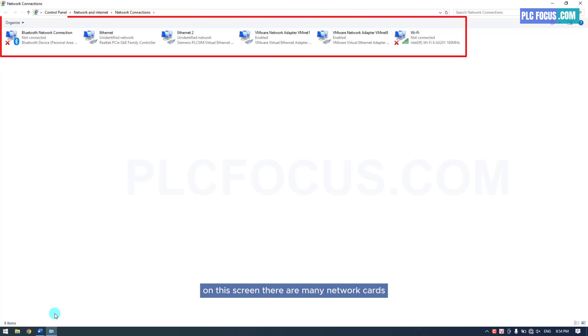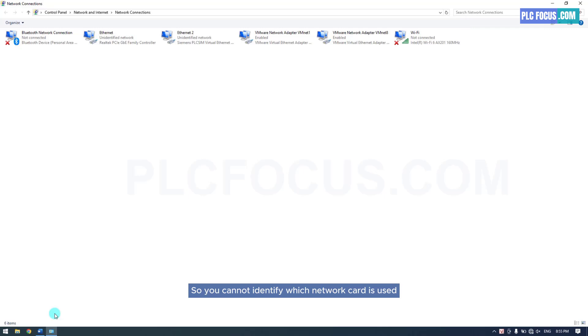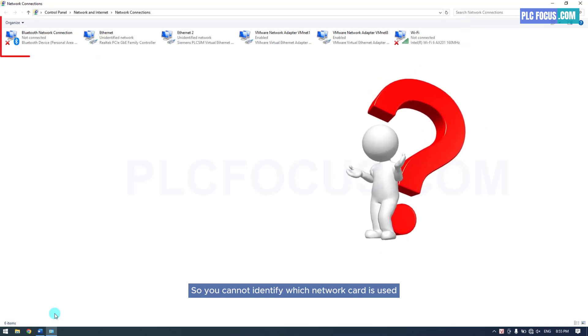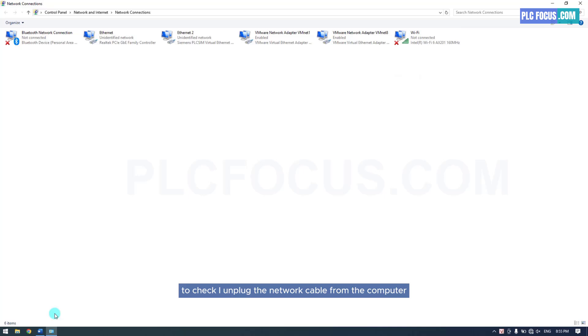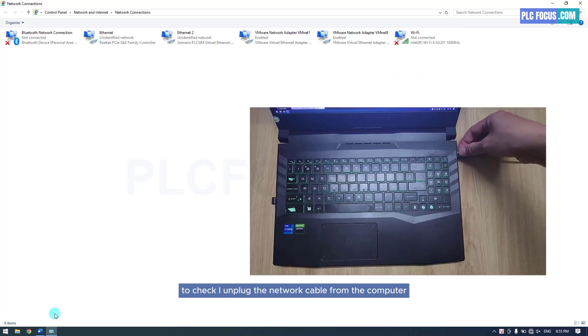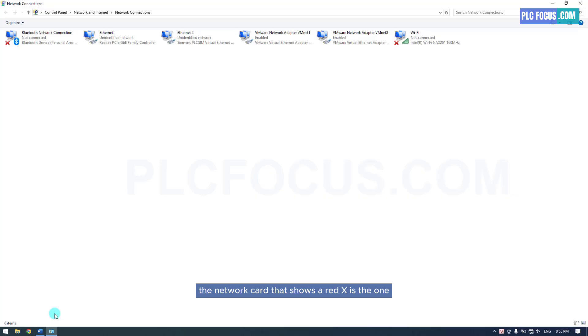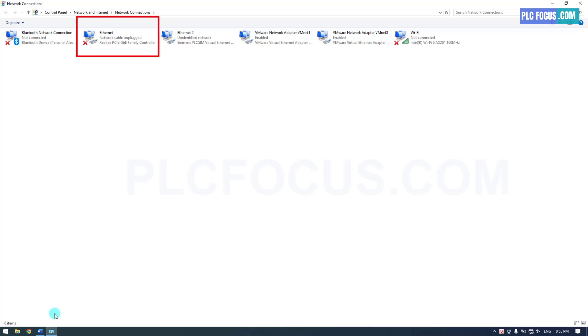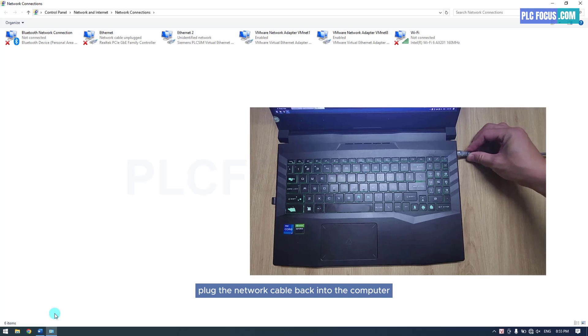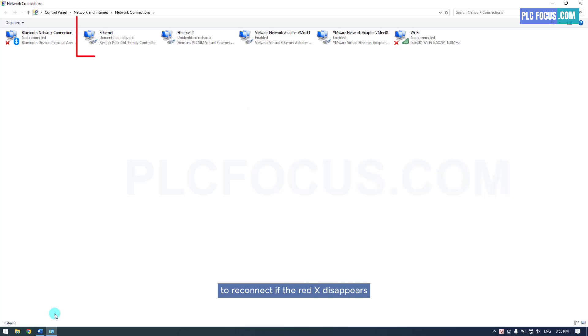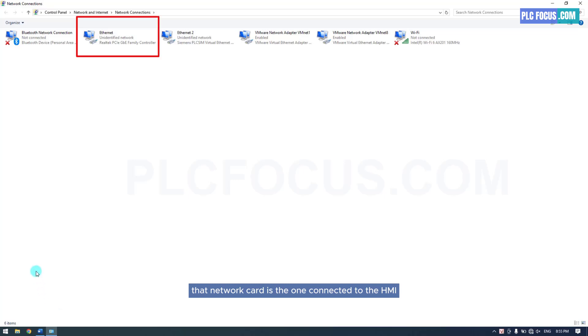On the screen there are many network cards, so you cannot immediately identify which one is used to connect to the HMI. To check, unplug the network cable from the computer — the network card that shows a red X is the one. Then plug the network cable back in; if the red X disappears, that network card is the one connected to the HMI.